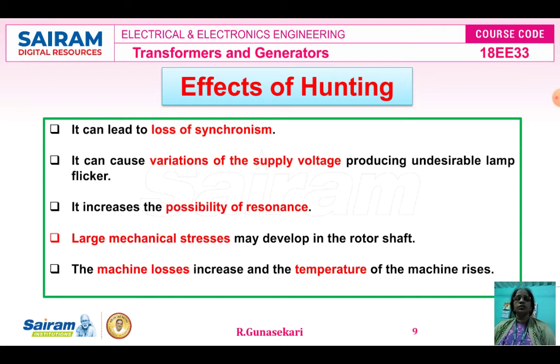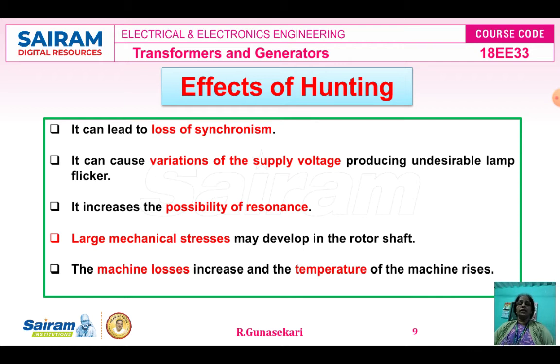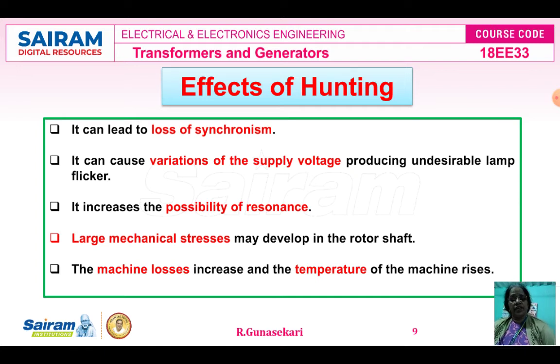The third effect is the possibility of resonance. Due to the effect of hunting, the possibility of resonance increases. If the frequency of the torque component becomes equal to that of the transient oscillation of the synchronous machine, resonance may take place. Additionally, due to hunting, large mechanical stresses develop in the rotor shaft, and the machine losses and temperature also rise.